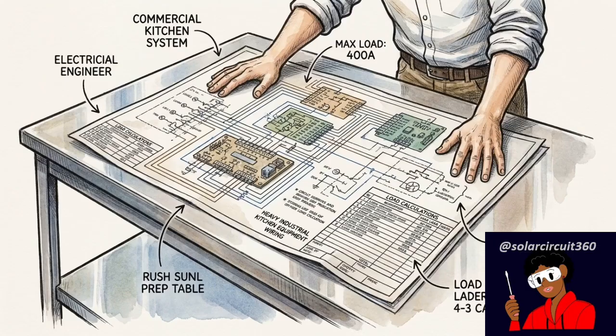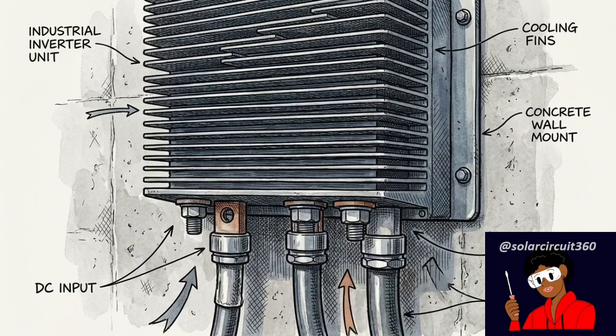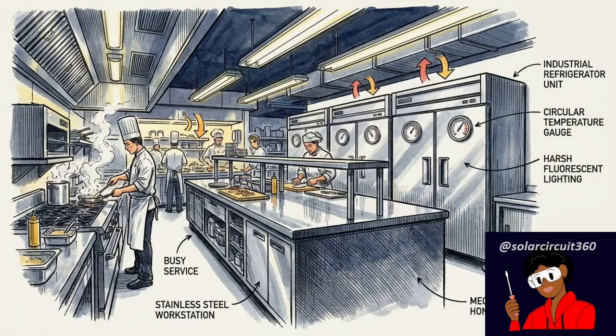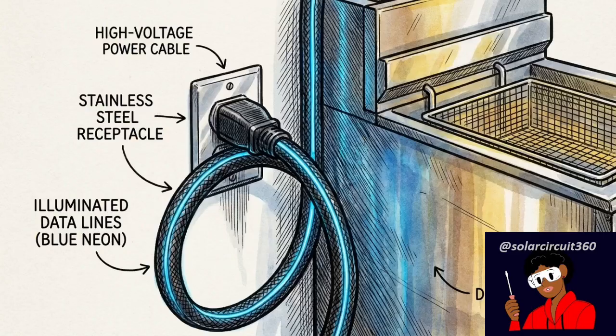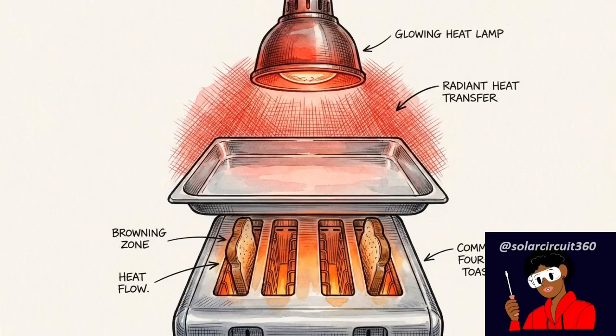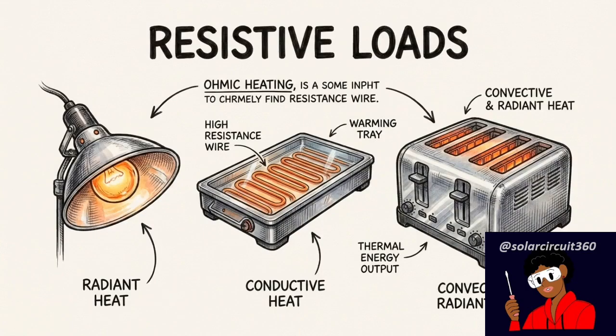Basic addition is useless here. Keeping a restaurant powered means engineering a system that can absorb extreme thermal loads and massive transient spikes without breaking a sweat. To understand why a 10 kilowatt inverter suddenly trips under an 8 kilowatt load, we have to look at the exact types of electrical loads sitting inside a kitchen. Some equipment draws a stable, resistive load. Heat lamps, warming trays, and commercial toasters fall into this category.